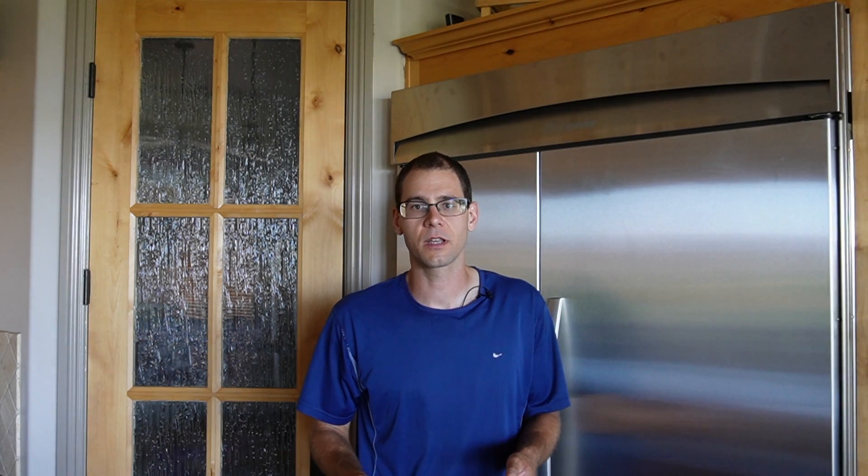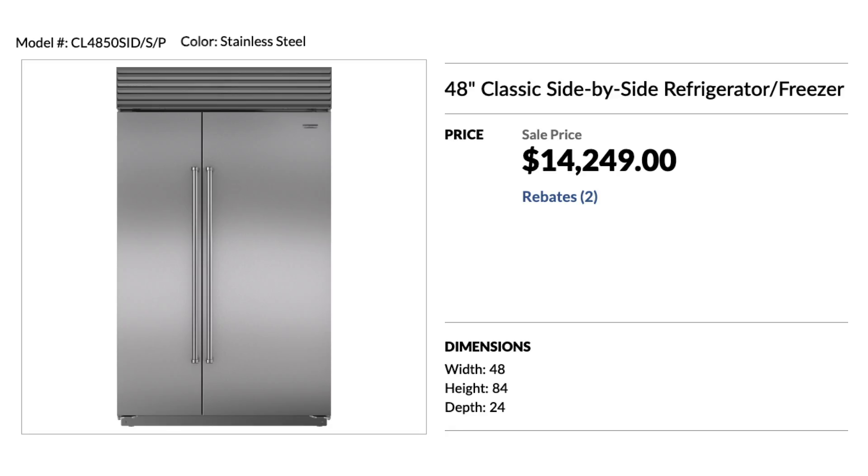The question is why? This could be an issue with low refrigerant, some type of internal short in the compressor in which case it would need to be replaced, or it could just be the relay switch that turns the compressor on. We need to go through this troubleshooting process and figure out exactly what's wrong, and I really hope we can because this refrigerator would cost over $10,000 to replace.